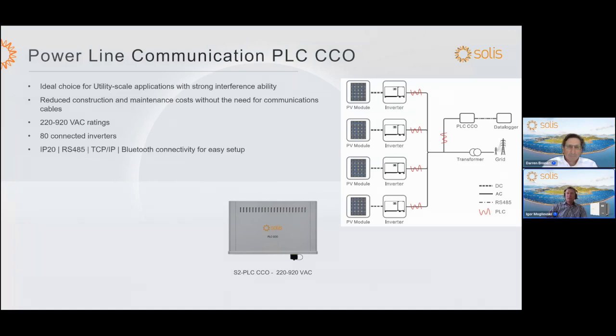It's an IP20 enclosure with RS-485, TCP/IP, and Bluetooth connectivity for easy setup. So you can choose your communication and configure the PLC device through Bluetooth. An external data logger can be connected to a third-party controller, and the baud rate is settable from 9600 to 115200.